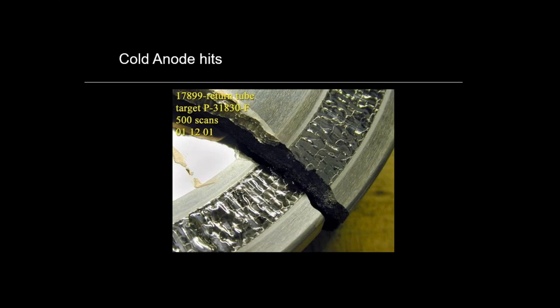One thing I didn't mention is that you have low speed tubes and high speed tubes. Low speed tube spins at 3,000 RPM. High speed tube spins at 10,000 RPM. A little bit of variation there. I think your 50 hertz is a little bit different, but generally that's how it is. Some CT tubes spin at one, but if you're putting high speed power through the tube and it's actually hooked up to low speed and not running that speed, you'll get damage to it.